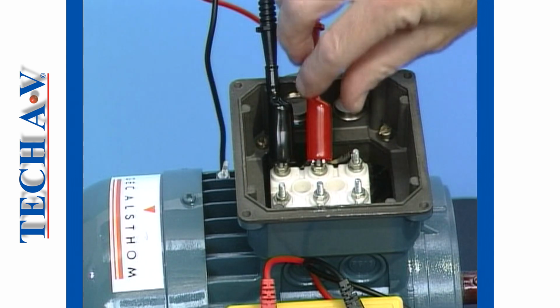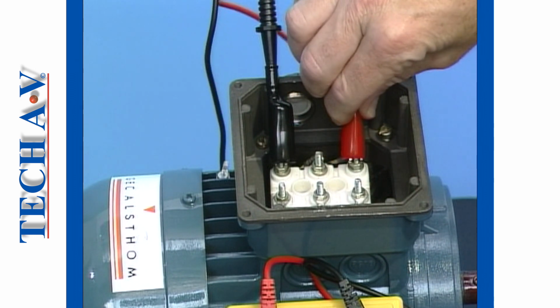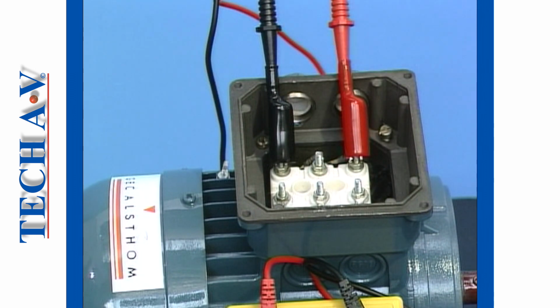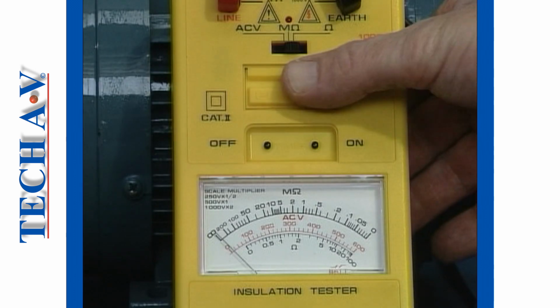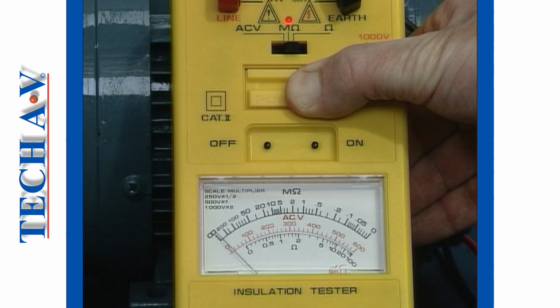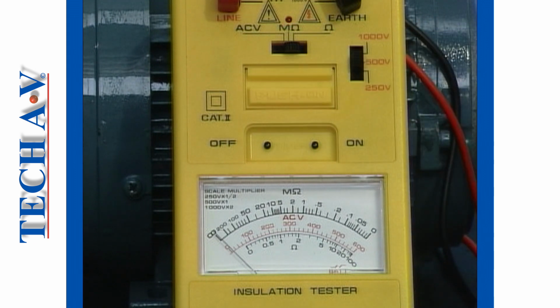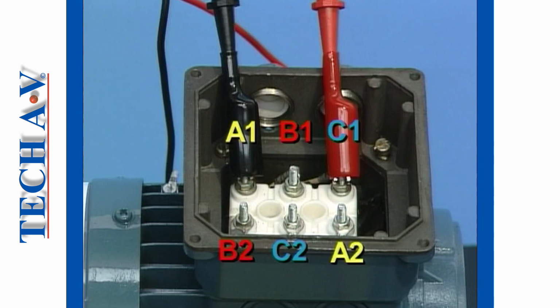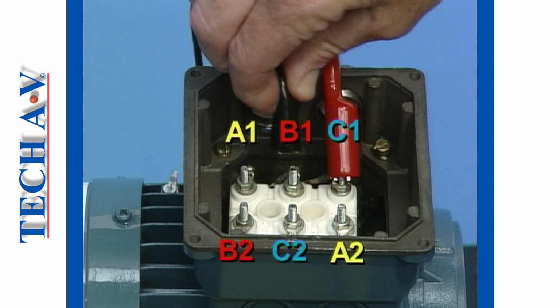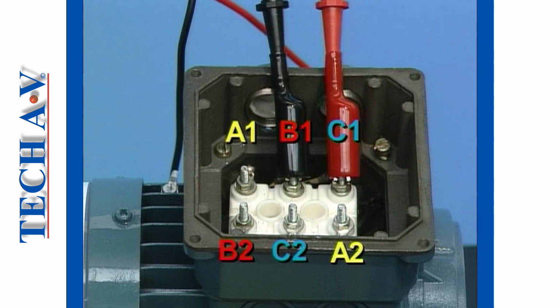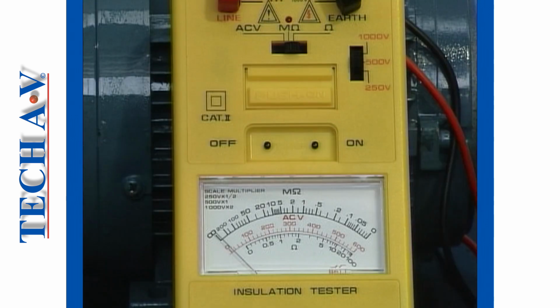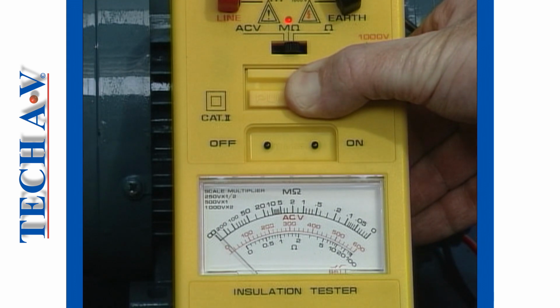Now unclip the Megger lead from B1 and connect it to C1. Test the insulation resistance again. The reading obtained must be greater than 1 megohm to be acceptable. Remove the test lead from A1 and connect it to B1. Once again, test the insulation resistance between the windings B1 and C1 and check that the reading is greater than 1 megohm.